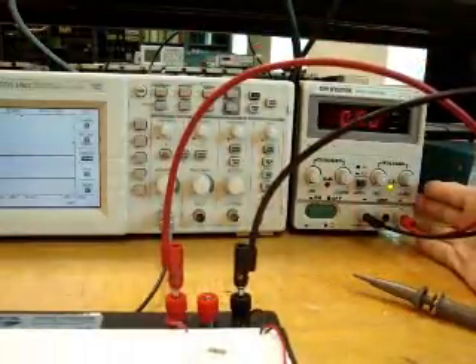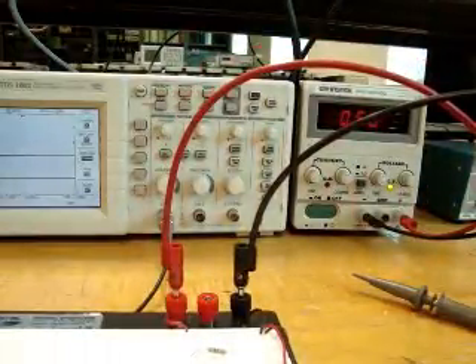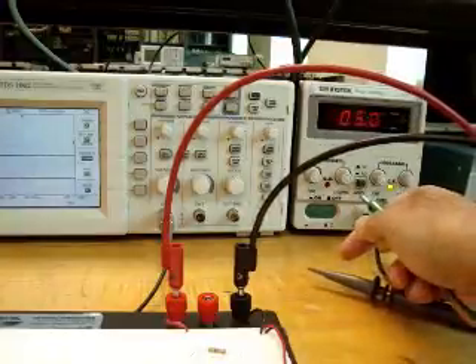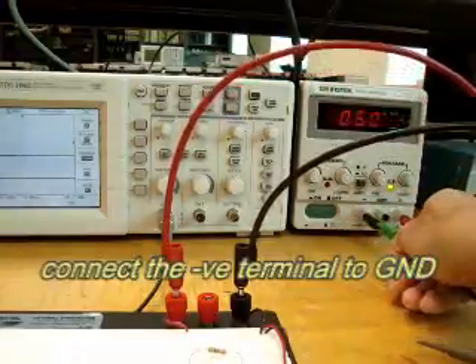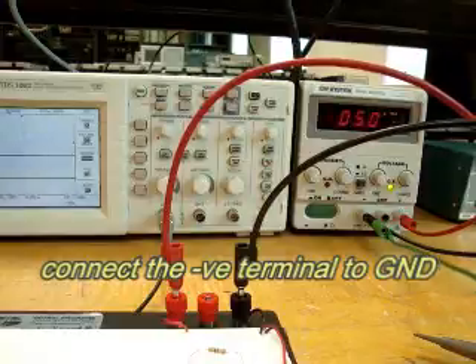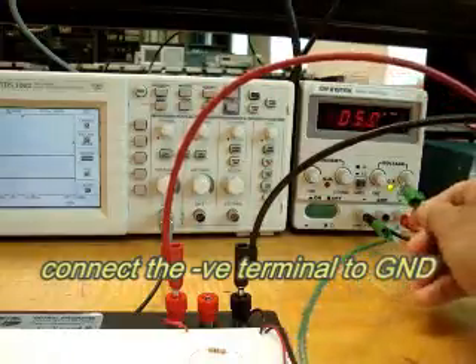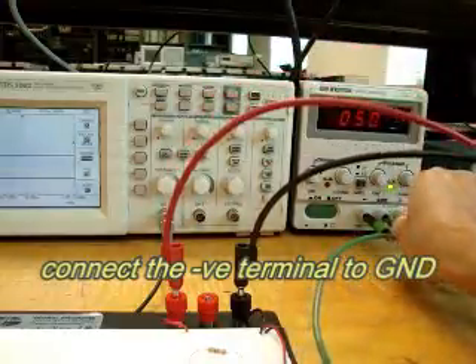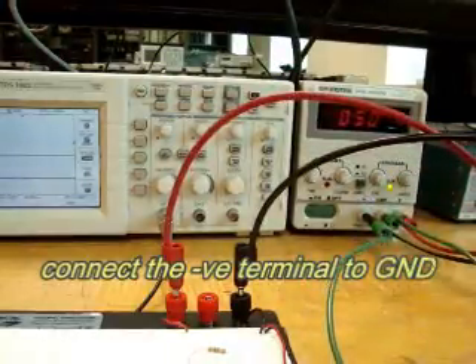Because this is a floating DC supply, we would like to reference our negative output to earth ground. So we will connect a jumper cable from safety ground to the negative terminal.